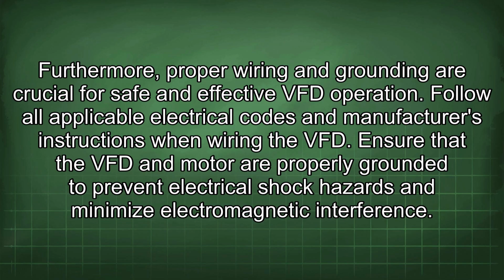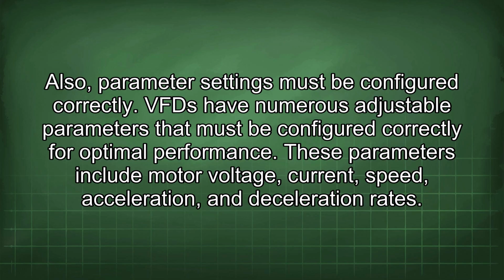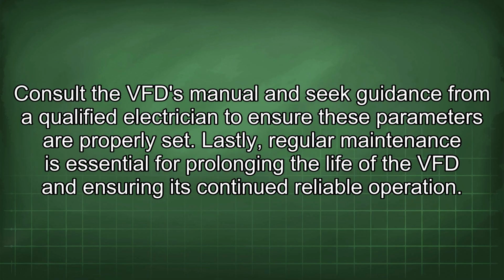Furthermore, proper wiring and grounding are crucial for safe and effective VFD operation. Follow all applicable electrical codes and manufacturer's instructions when wiring the VFD. Ensure that the VFD and motor are properly grounded to prevent electrical shock hazards and minimize electromagnetic interference. Also, parameter settings must be configured correctly. VFDs have numerous adjustable parameters that must be configured correctly for optimal performance. These parameters include motor voltage, current, speed, acceleration, and deceleration rates. Consult the VFD manual and seek guidance from a qualified electrician to ensure these parameters are properly set.